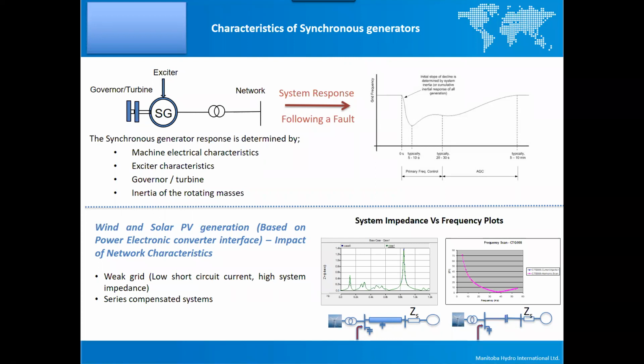What I mean by the condition of your network is the impedance of the network, both at 50 Hertz, which is generally referred to as the fault level of the system at that particular location, as well as the resonant conditions of your network. The resonant conditions are simply the impedances seen from a particular point, in this case the point where you connect wind or solar. Looking into the network from that point, you see impedances at other frequencies, and if you plot them, you get curves like this, where you identify the so-called parallel resonant points and series resonant points of your network.